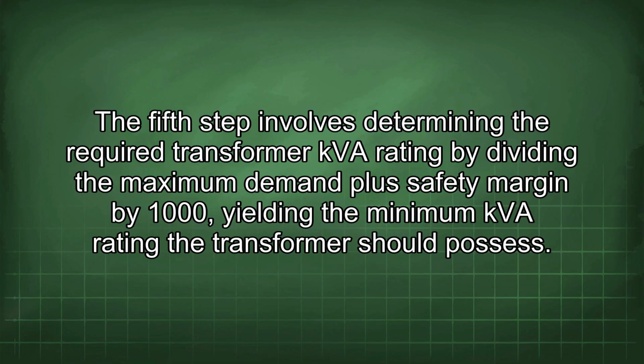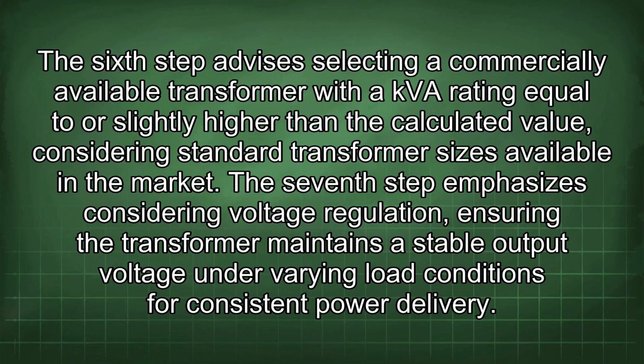The fifth step involves determining the required transformer kVA rating by dividing the maximum demand plus safety margin by 1000, yielding the minimum kVA rating the transformer should possess. The sixth step advises selecting a commercially available transformer with a kVA rating equal to or slightly higher than the calculated value, considering standard transformer sizes available in the market.